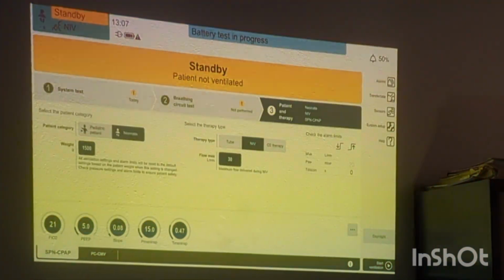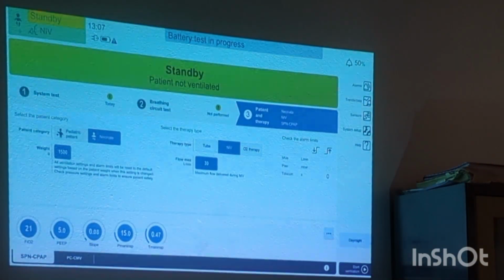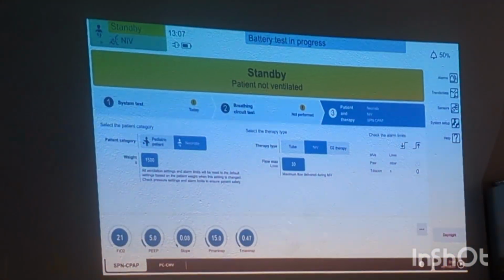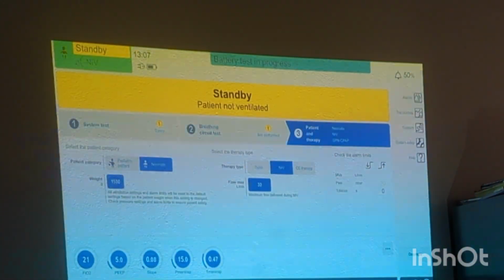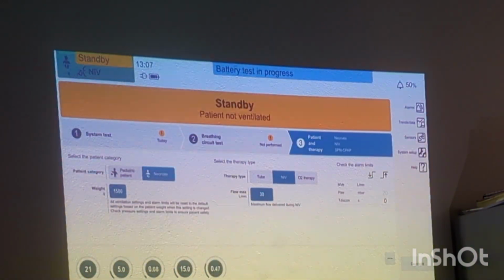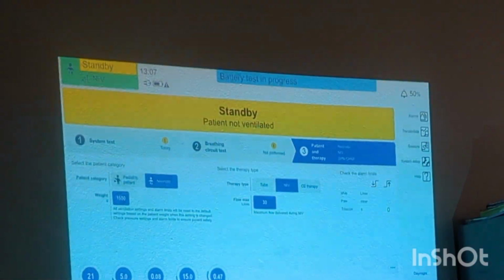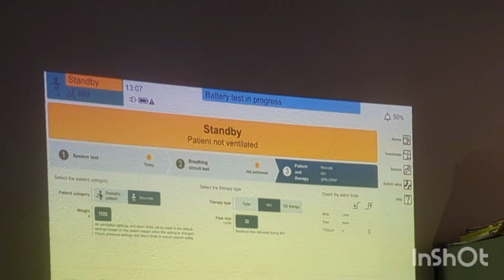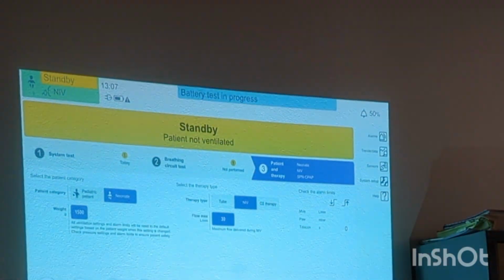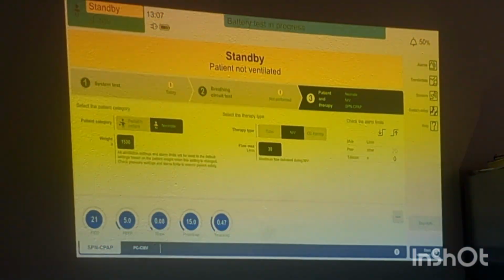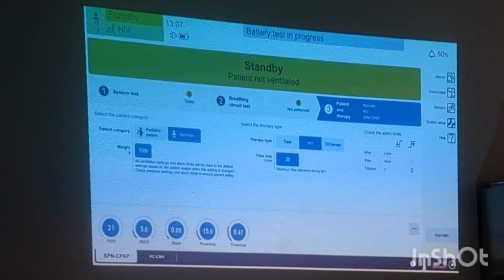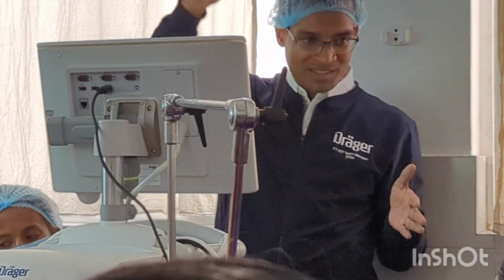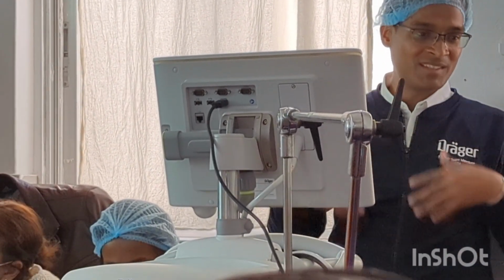So if you will use a mask and you are not using flow monitoring, you select this mode. But in case you still want to use NIV and you are okay with all these alarms, because even in other ventilators the monitoring is not accurate, and you want to put your flow sensor and use the nasal prongs, the flow will not come back. Also what we have seen is that if you are using very long nasal prongs, even if it is not connected to the patient, you can see nice graphs and nice ventilation. Actually it is only because of this resistance that the pressure is getting created.